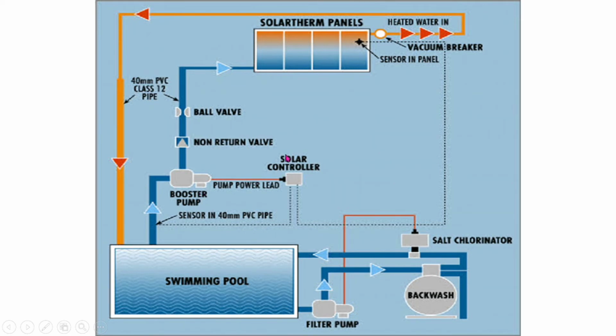It is normal, you can see in houses it is being installed, so we have to use the collector only. With this collector the hot water will go directly to the swimming pool, and there are booster pump valves. This is the solar controller to control the temperature, the sensor at this pipe, and the return, at what temperature it is coming. If it is low, then the booster pump will start working and it will go through the solar. And this is the filtration system.